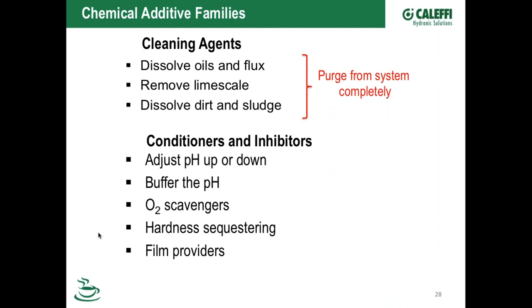And then if there is a little bit of residual hardness from the water, one of the chemicals in those corrosion inhibitors, I think the word is flocculant, keeps those minerals in suspension. So instead of the minerals falling out of solution and scaling out, if you drain the water out of a boiler with that type of chemical, the water looks really dirty and gray or brown colored. That's because the chemical is keeping all those deposits in solution so they don't scale out on the surfaces of your boiler and your heat exchangers, your pumps and stuff like that.